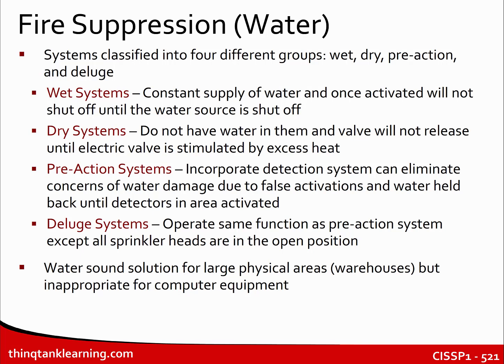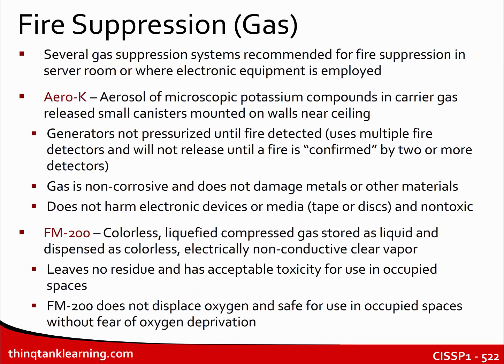A pre-action system incorporates detection systems that can eliminate concerns of water damage because of false activations. The water is held back until the detectors in the area are activated. And you could have multiple detectors, and in order for that pre-action system to be triggered, multiple events would have to occur. Deluge systems operate the same as a pre-action system, except every sprinkler head is in the open position. So as soon as the water starts running, it's going to go into every system. Water is okay for things like warehouses and whatnot, but as you can imagine, it's somewhat inappropriate for electrical equipment and computer rooms.